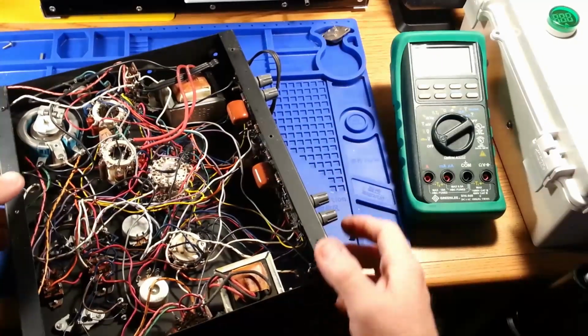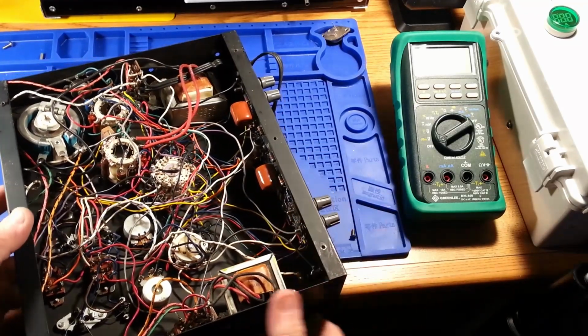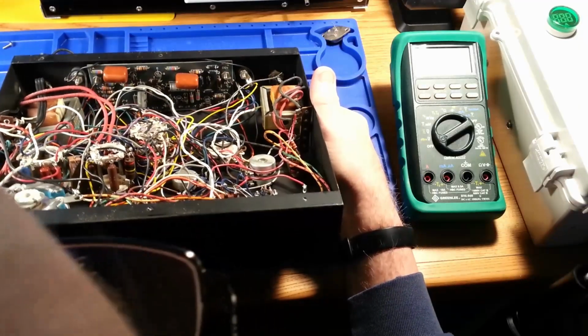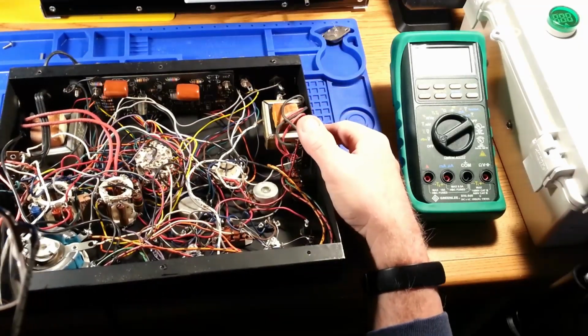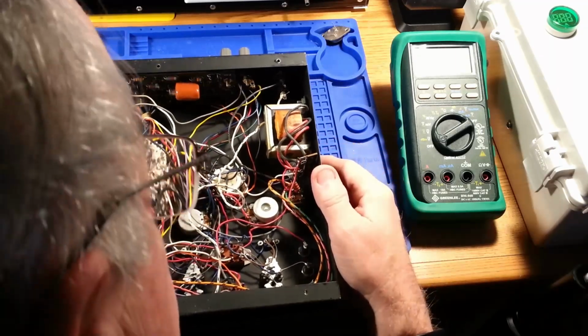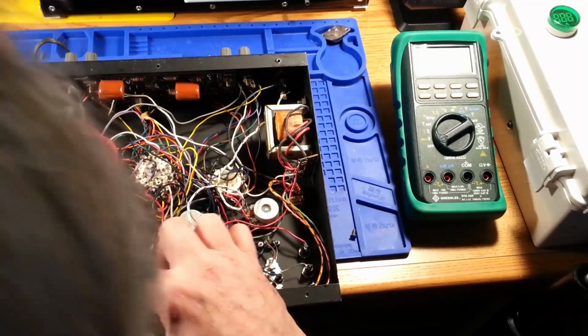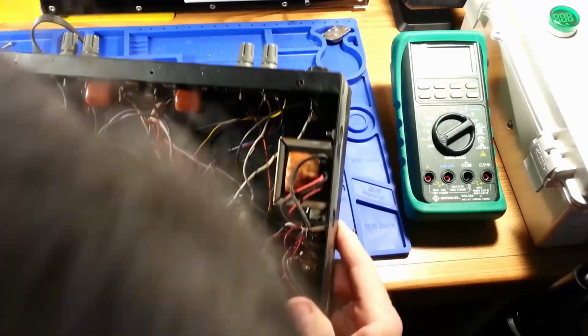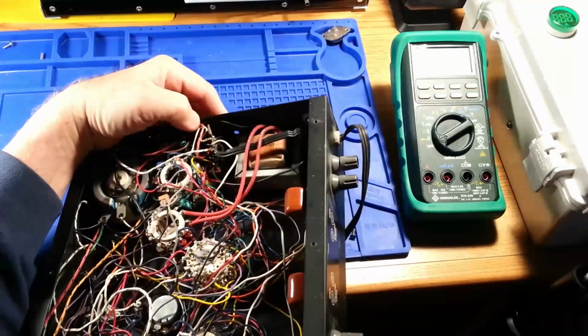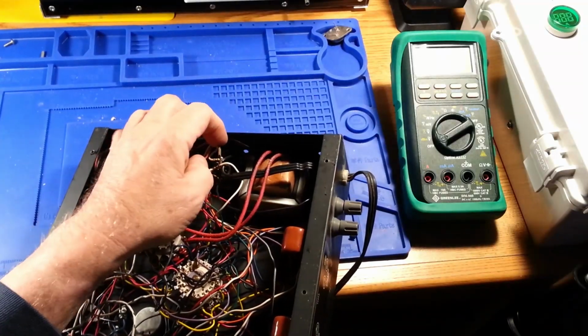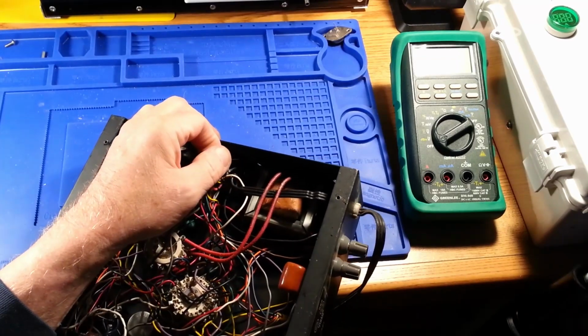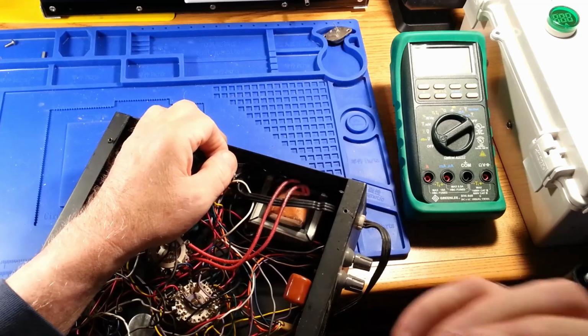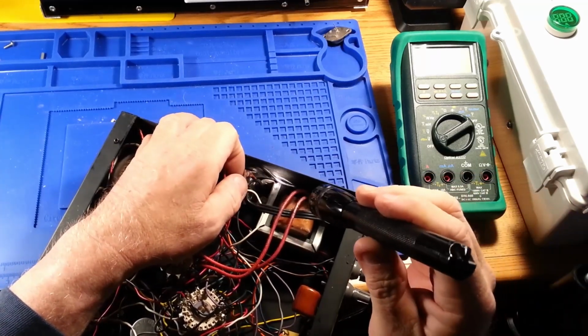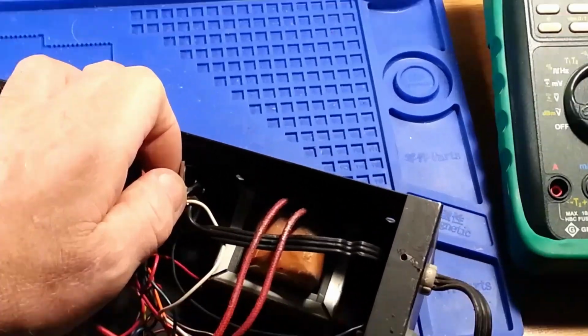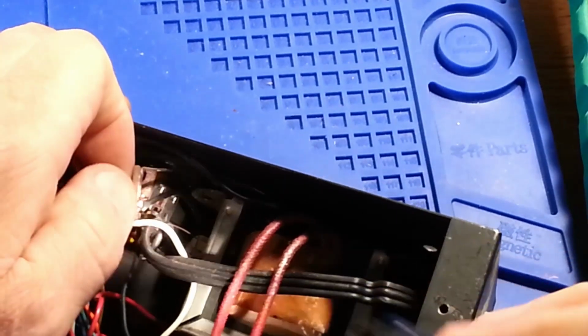As far as the board's concerned, this one board is definitely a newer version. Doesn't look like anybody's been poking around in here either. Oh, there's another something that happened on the way here. This one's got a broken terminal strip. Let me get some lighting here. This terminal strip was probably mounted on the hole for the transformer. And what happened was when the hardware came loose, that transformer knocked around enough to crack it.